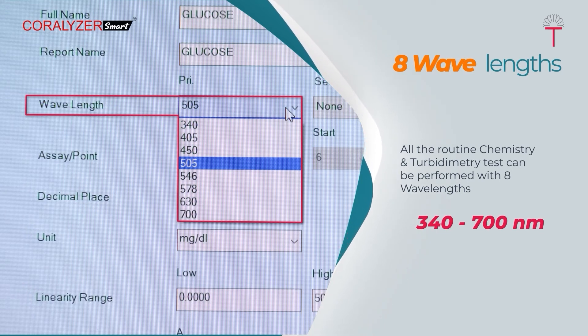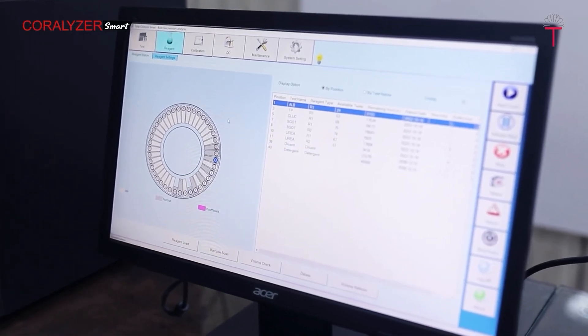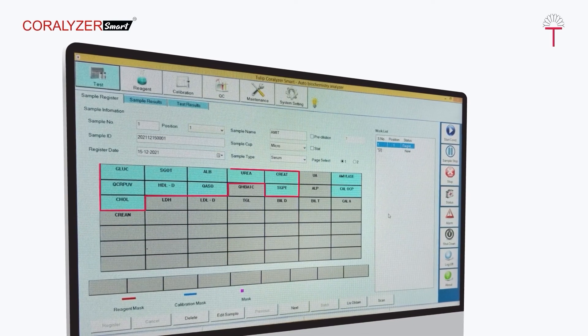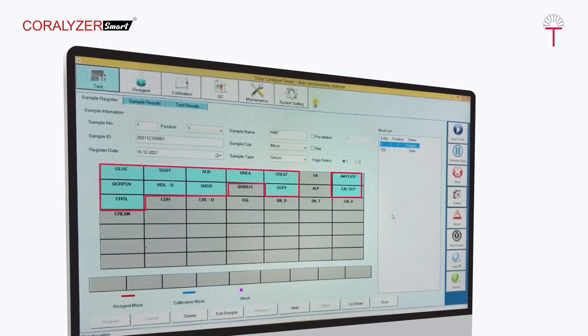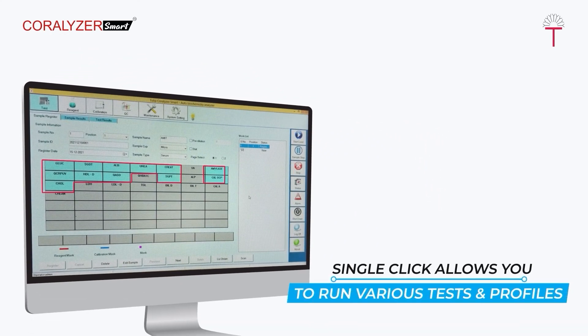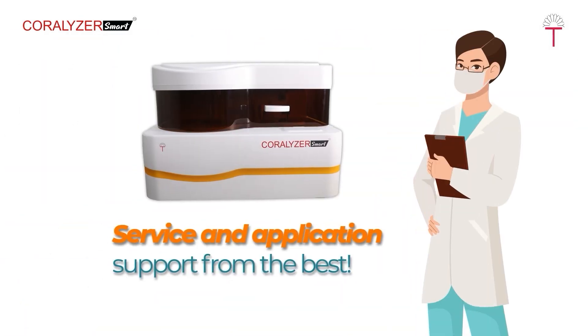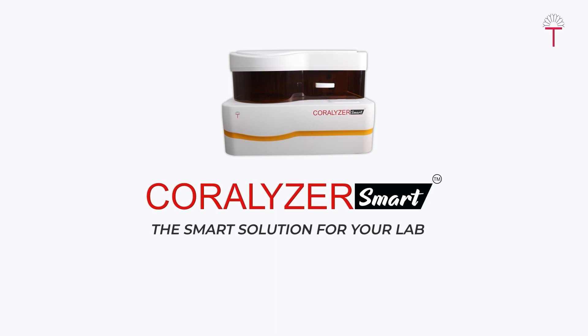All routine chemistry and turbidimetry tests can be performed with eight wavelengths ranging from 340 to 700 nanometres. The user-friendly software application features easy navigation and a dashboard where parameters can be automatically calibrated and controls and samples run with a single command. A single click allows you to run various tests and profiles, monitor all operations on the dashboard, and access huge storage space for storing and retrieving patient and control data — backed by service and application support from Coralyzer Smart, the smart solution for your lab.